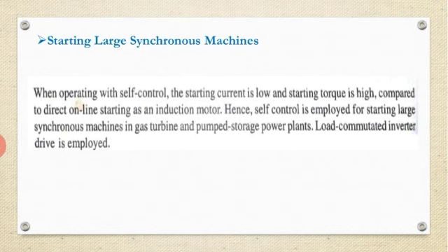In the last video lecture I discussed self control and true control of the synchronous motor. To overview: when operating with self control, the starting current is low and the starting torque is high compared to direct online starting as an induction motor. Hence self control is employed for starting large synchronous machines.